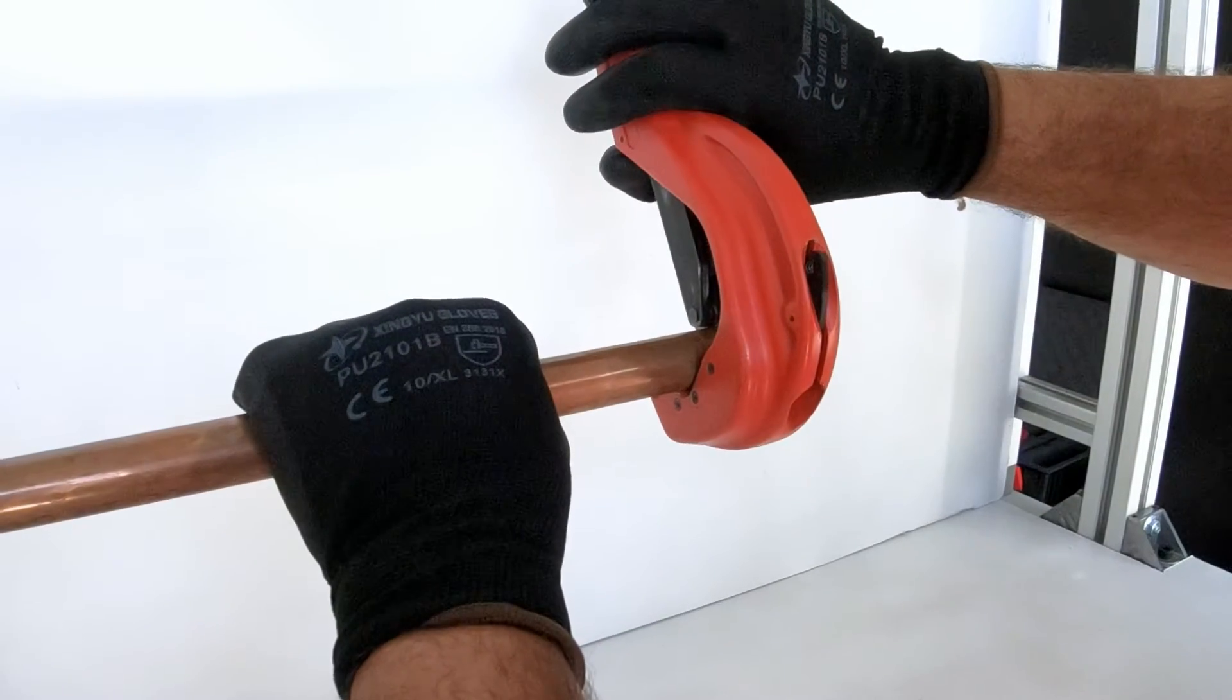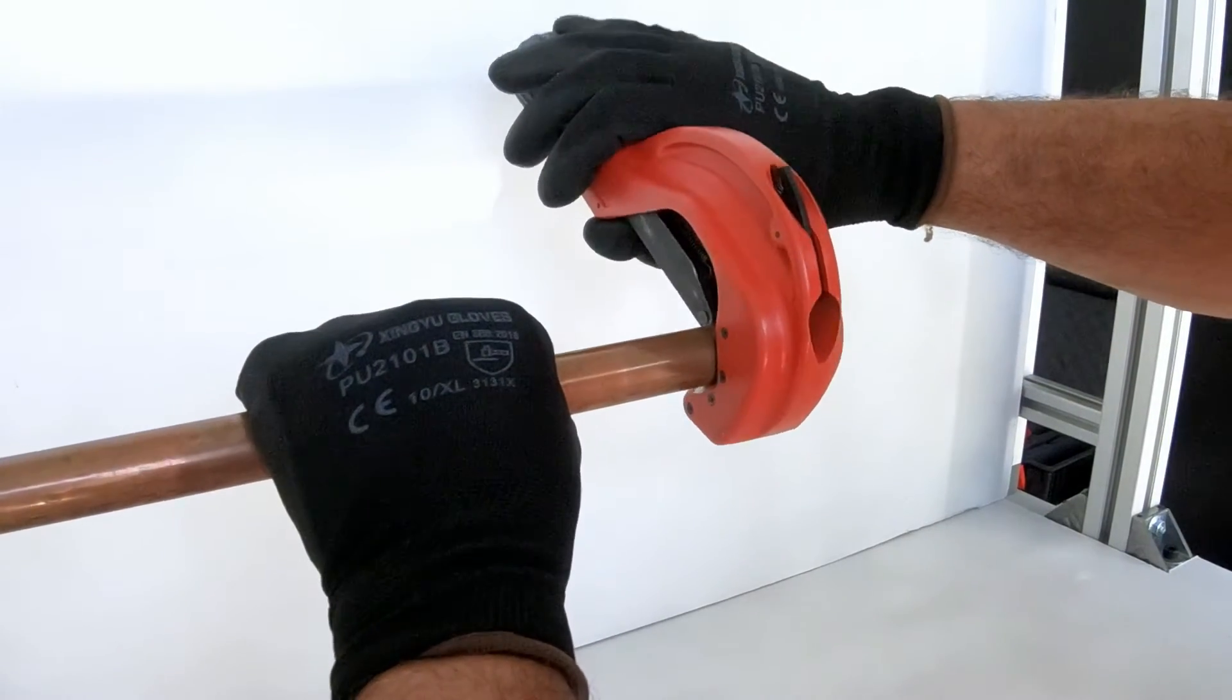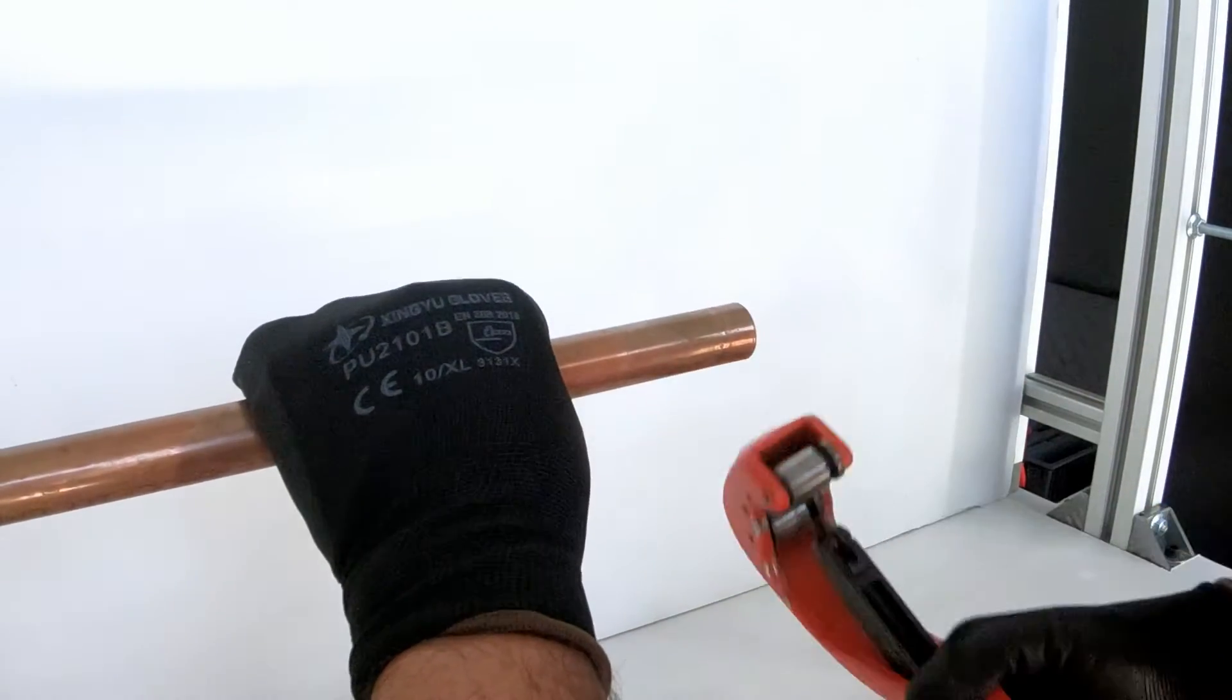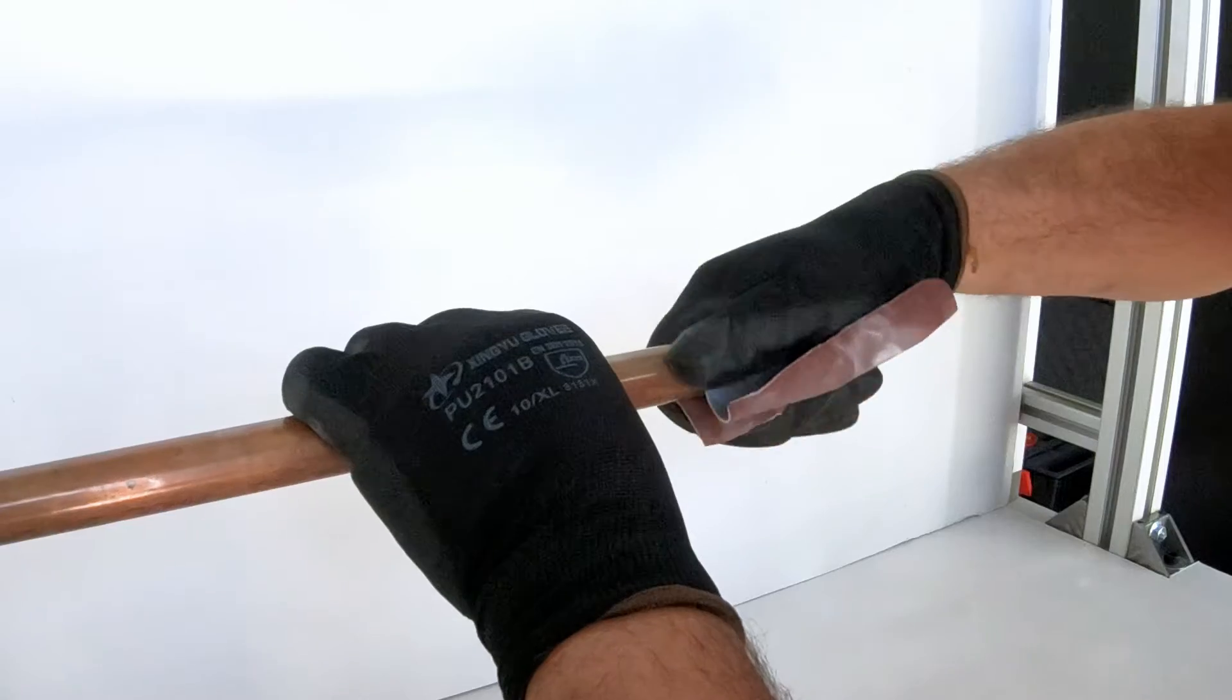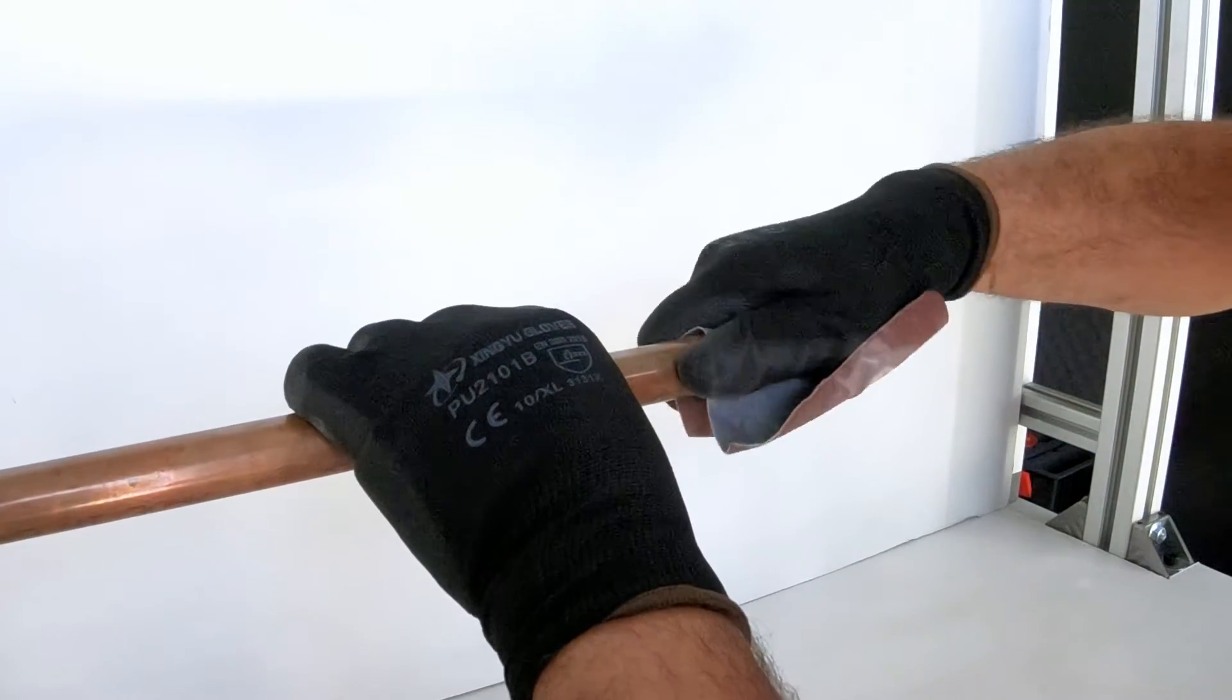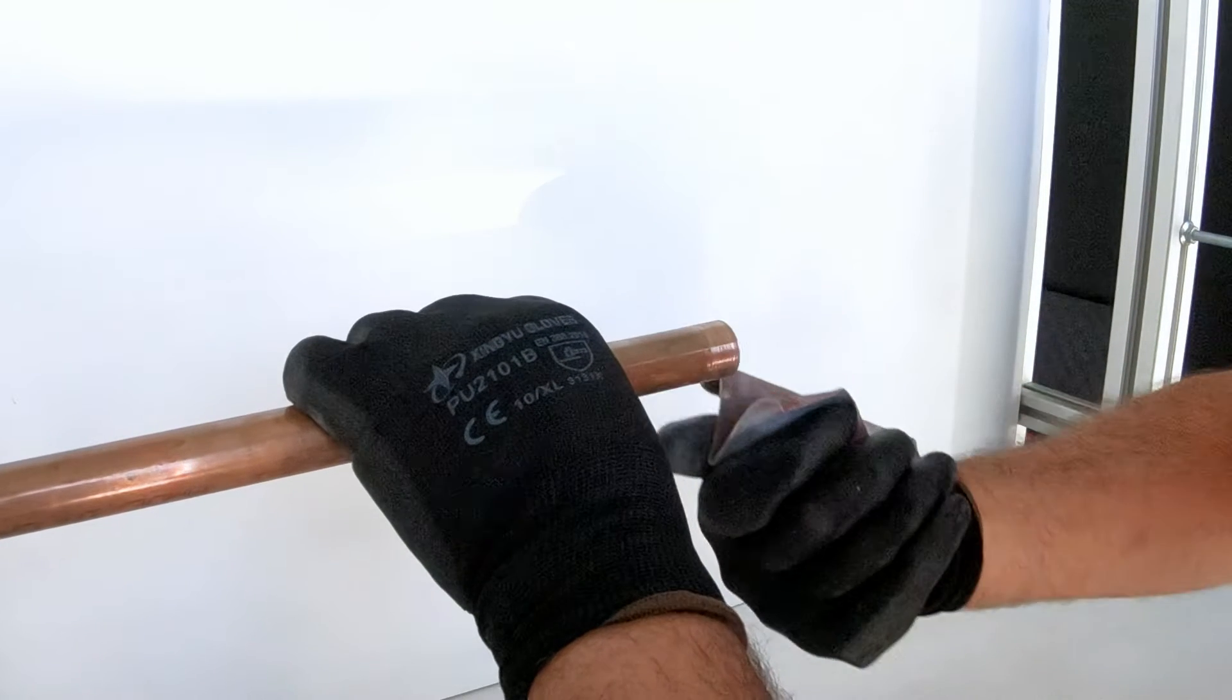Now before starting the installation, following ASTM B828 standards, properly measure and cut the pipes, ream all cut ends to remove any burrs, and clean all oxides from tube ends and valve cup surfaces. Tube ends should be lightly abraded to promote surface contact.